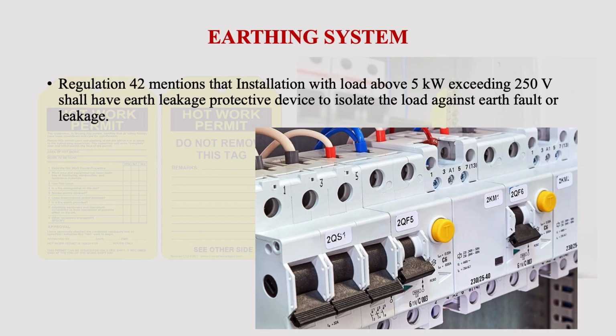or apparatus are energized. Now we are into the last part of our discussion, which is focused on earth leakage protecting devices for leakage current management for industrial safety. Regulation 42 mentions where an earth leakage protecting device should be employed. This regulation states that an installation with load above 5 kW exceeding 250 volts shall have a suitable earth leakage protective device to isolate the load in case of earth fault or earth leakage.